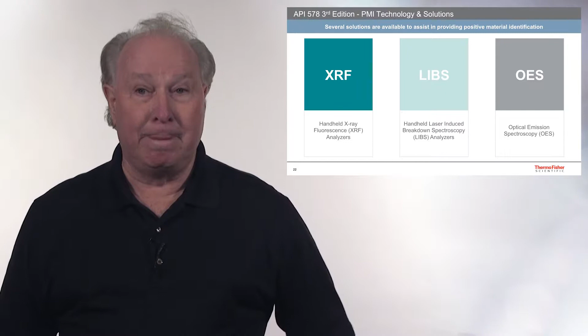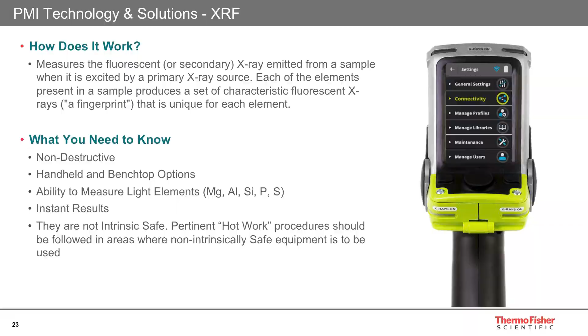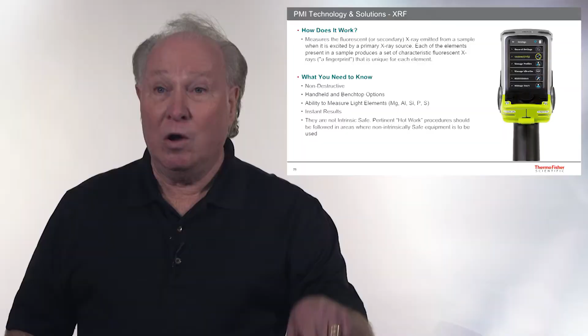What about that XRF analyzer? The best way it works is it sends out, with a little tube, it lights up and sends out an X-ray. It affects the electrons in the inner shell of that atom and they get ejected. When it does, it sends back electromagnetic energy into that analyzer in little pulses. Then that SDD, silicon drift detector, converts that to kilo electron volts. If you ever took chemistry, you might know what a KeV is - maybe you don't. But anyway, it compares it to an onboard library, does the calculations, and displays what's in that material. It's non-destructive, doesn't make a mark on the pipe.